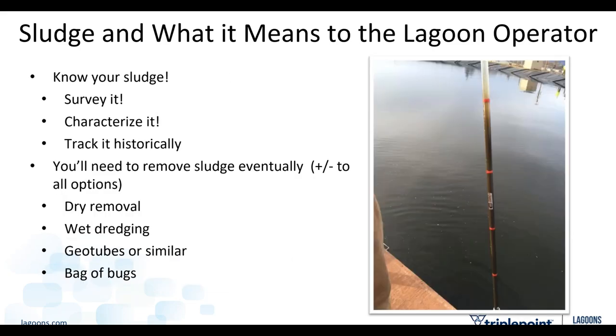And I think it's really important to be able to describe your sludge. You should survey it, characterize it, and you should track it historically. On the right side there, a picture of a sludge judge. That is a whole lot of sludge in that sludge judge, isn't it? That's a deep, deep sludge blanket there. A bit more than 18 inches, I think.